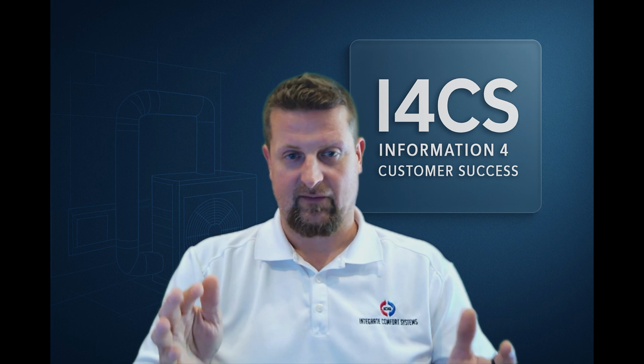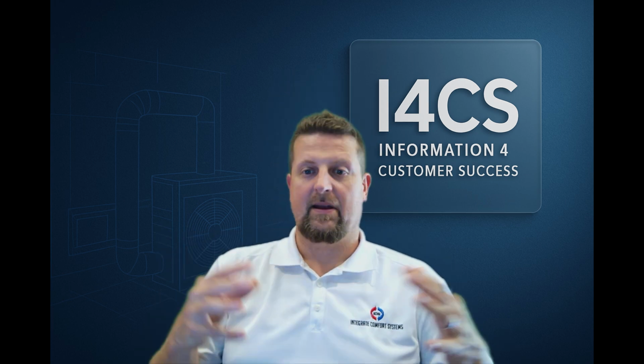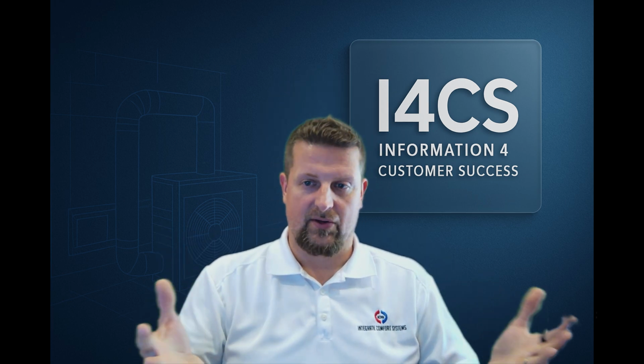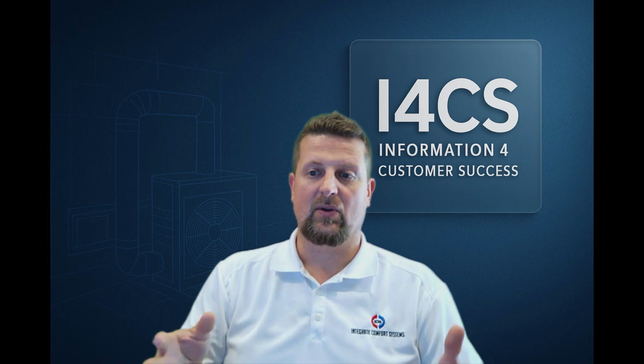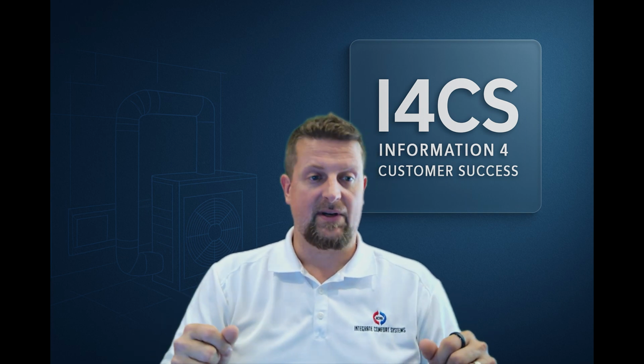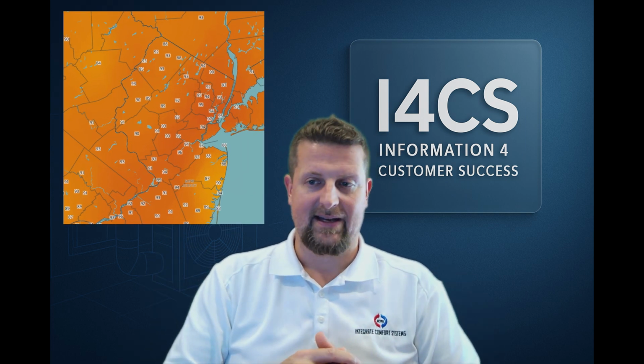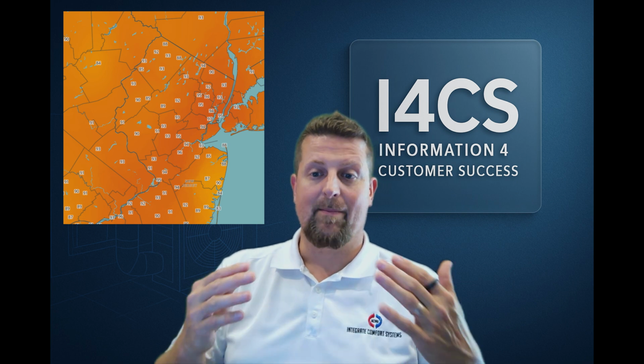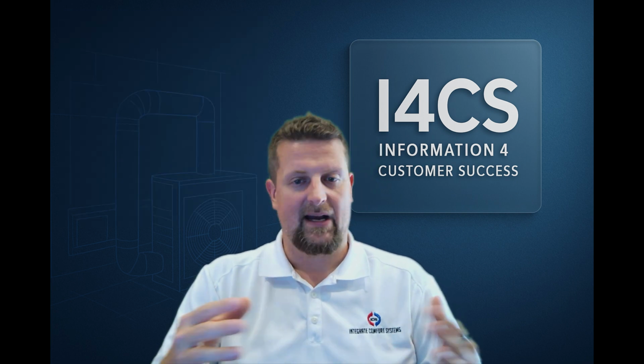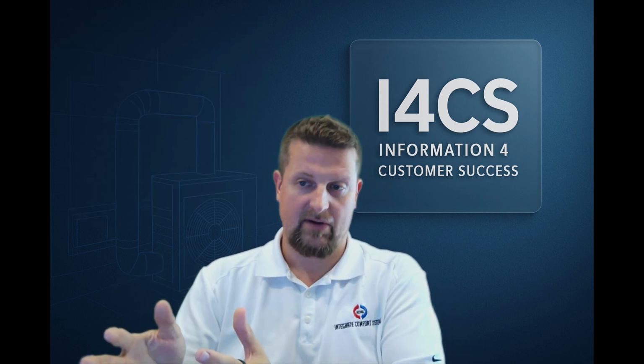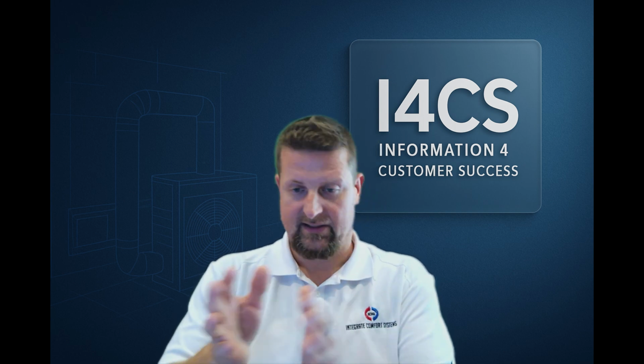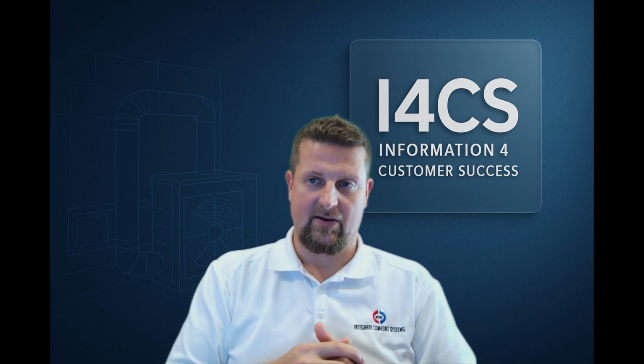We are not designing for those extreme days. So in our area, call it northern New Jersey here, ASHRAE lists the 1% cooling design temperature around 91 degrees. It varies on where, what part of the state exactly. So that's what Manual J is based on. But once we hit 96, 97, even 100 degrees, we're outside of that design spec. So what happens?